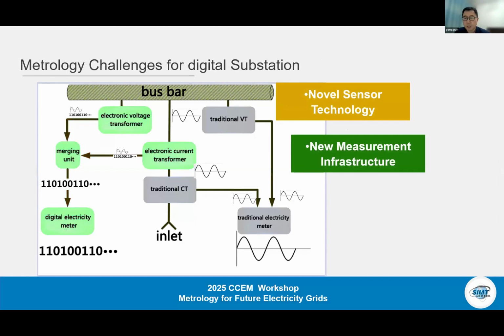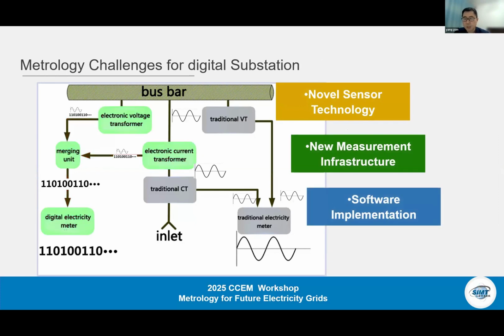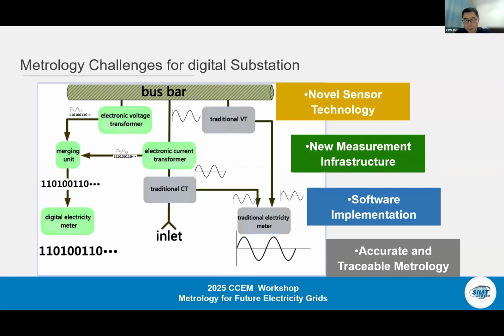The introduction of electronic instrument transformers and merging units in digital substations is presenting new challenges for traditional metrology systems. The shift from analog to digital measurement challenges established traceability chains primarily based on analog signals. The key issues that metrology institutes are currently addressing include the accurate calibration and verification of digital output signals, ensuring precise time synchronization and characterizing the phase displacement introduced by the electronic instrument transformers and merging units, all of which impact the overall accuracy and reliability of energy measurements in the evolving smart grid landscapes.